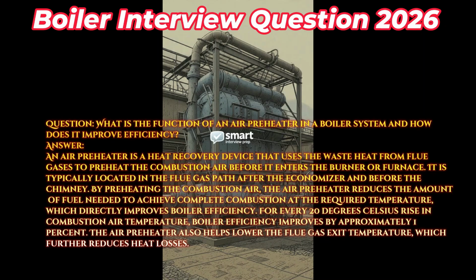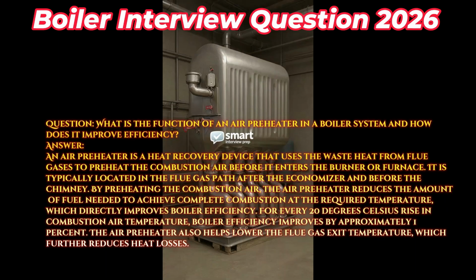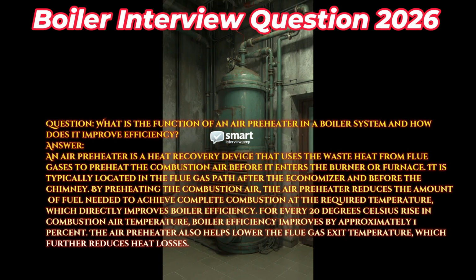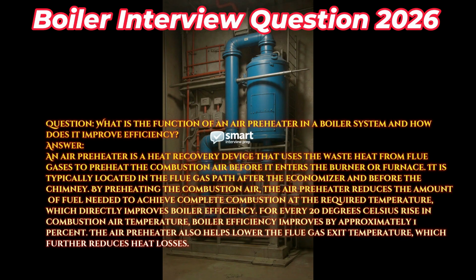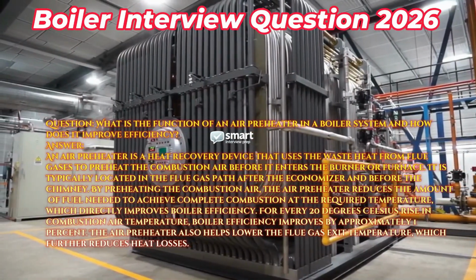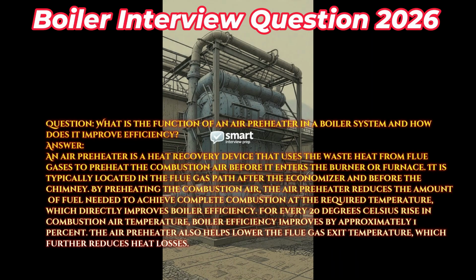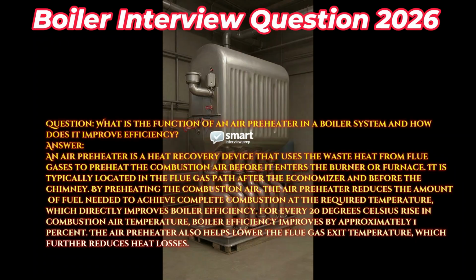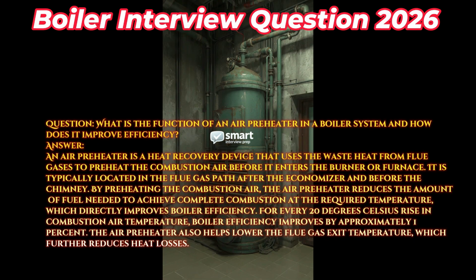Question: what is the function of an air preheater in a boiler system and how does it improve efficiency? Answer: an air preheater is a heat recovery device that uses the waste heat from flue gases to preheat the combustion air before it enters the burner or furnace. It is typically located in the flue gas path after the economizer and before the chimney. By preheating the combustion air, the air preheater reduces the amount of fuel needed to achieve complete combustion at the required temperature, which directly improves boiler efficiency. For every 20 degrees Celsius rise in combustion air temperature, boiler efficiency improves by approximately 1%. The air preheater also helps lower the flue gas exit temperature, which further reduces heat losses.